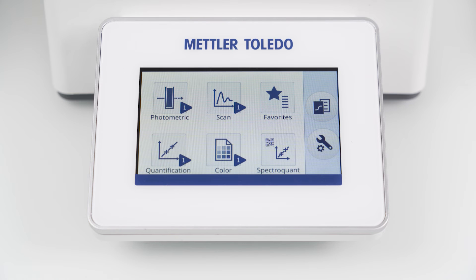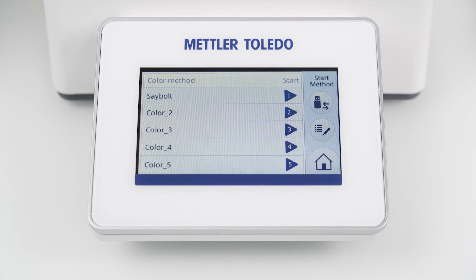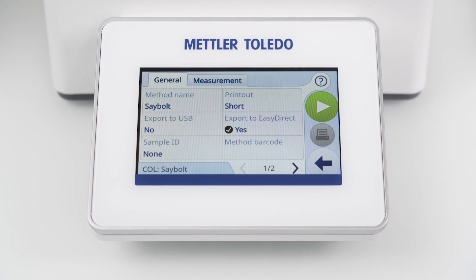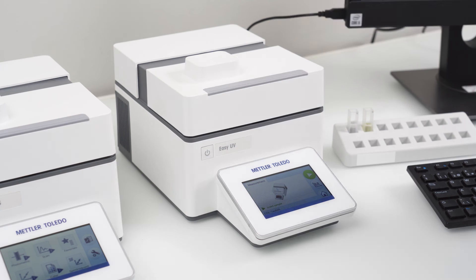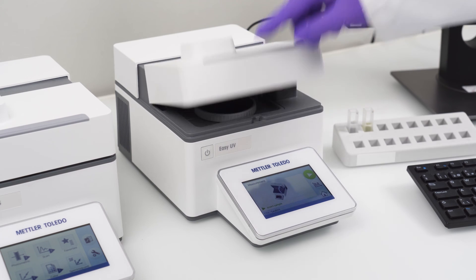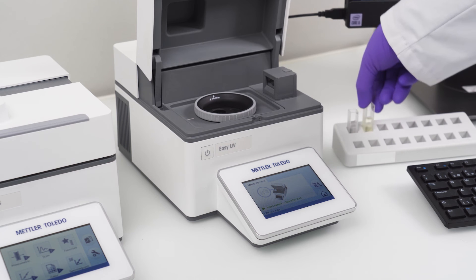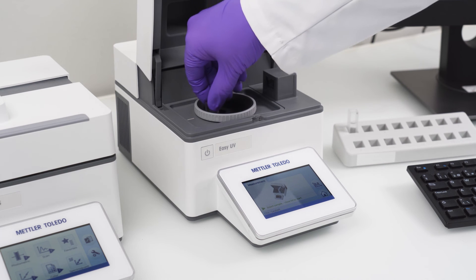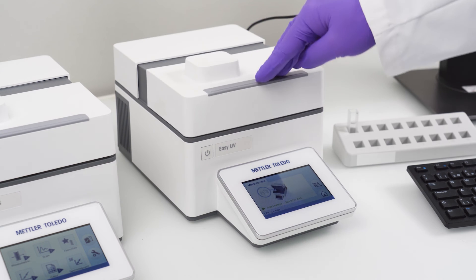If you are regularly measuring color samples according to different color scales the EasyDirect UV-VIS software can save you precious time as it can show multiple color results out of a single measurement. Let me quickly demonstrate this to you. I have here a yellowish sample from which I want to determine the color according to the Saybolt and ASTM color scale.